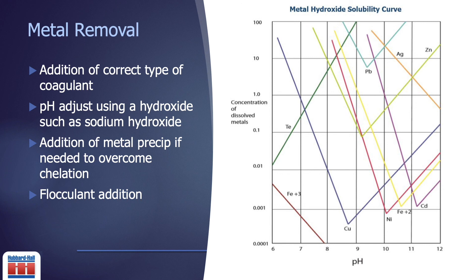Depending on the metals needed to be removed, the pH can be lower or higher. Nickel comes out best at a pH of 10.5, while chrome is removed at a pH of 9. The object is to find the pH range where all of the metals would form hydroxide salts and fall out equally. If the waste stream has more of one metal than the other, the pH would then be adjusted more toward the pH of the prominent metal. Once pin flock is formed, a flocculant will need to be added to clump the pin flock together to form larger flock that will settle rapidly in a quiet tank or clarifier. Most often, the flocculant will have an anionic or negative charge to attract the positive charge of the metals. Flocculants can come in emulsion, dry, or ready-to-use forms. If it is an emulsion or dry form, it is typically made down to a 0.1 to 0.2% dilution in a day tank or blending unit prior to being added to the system.